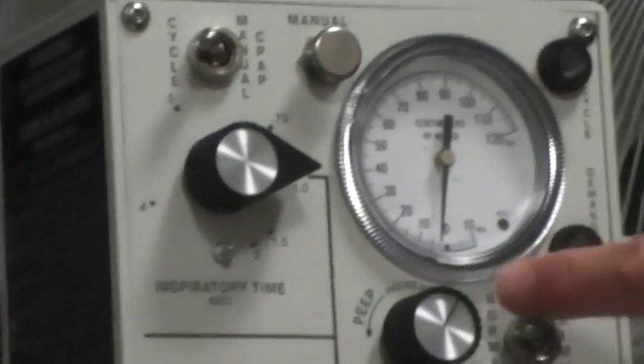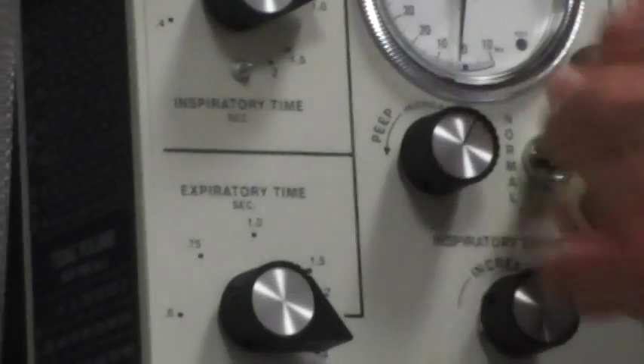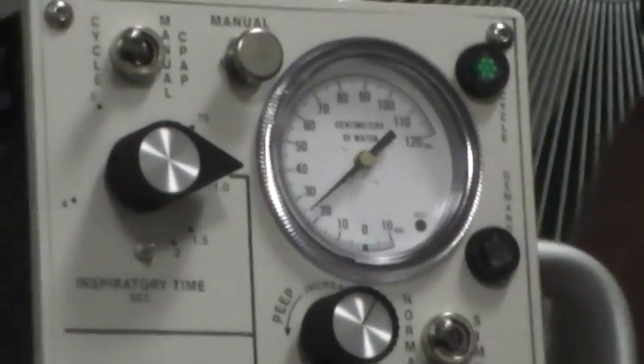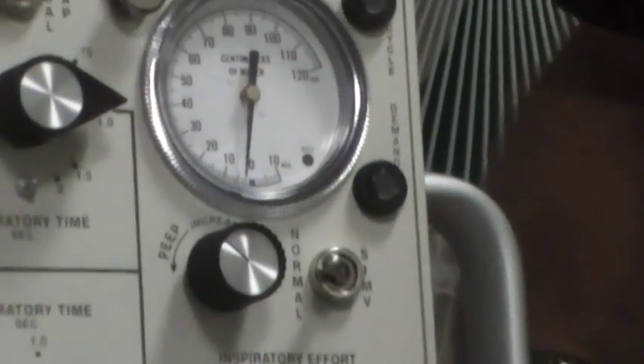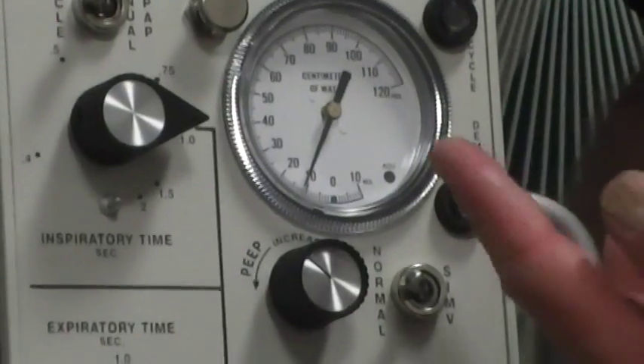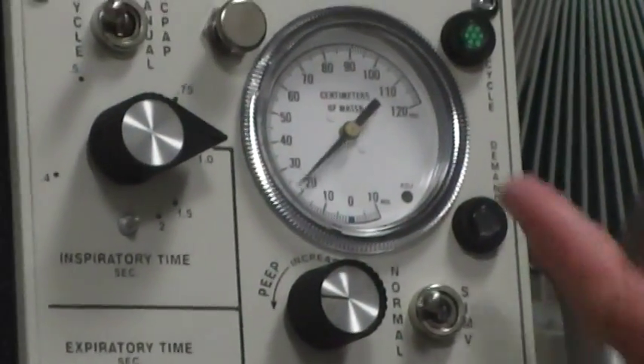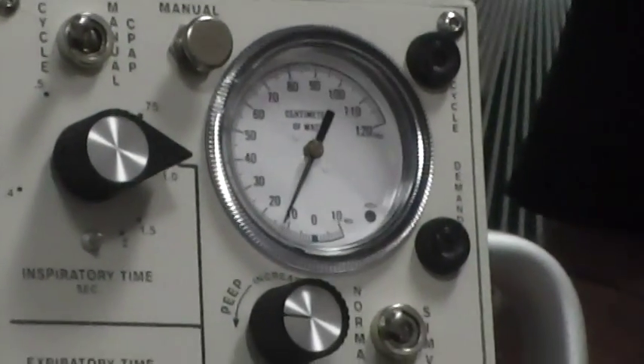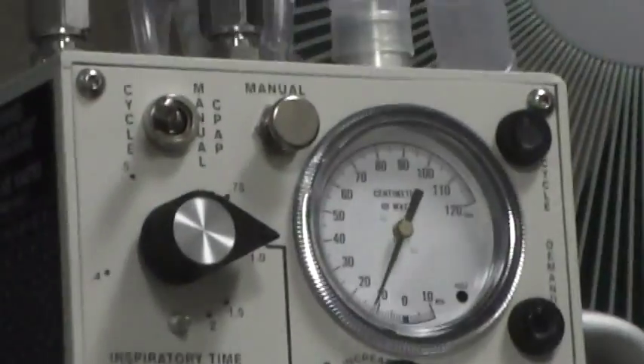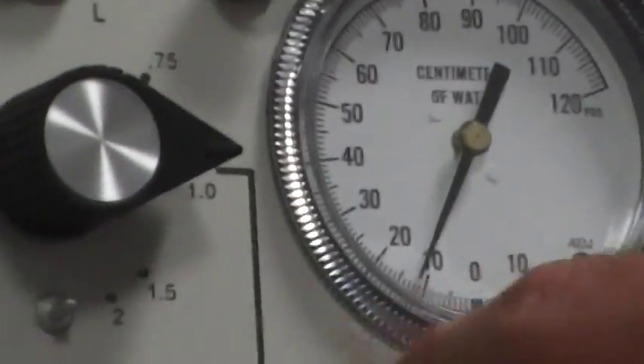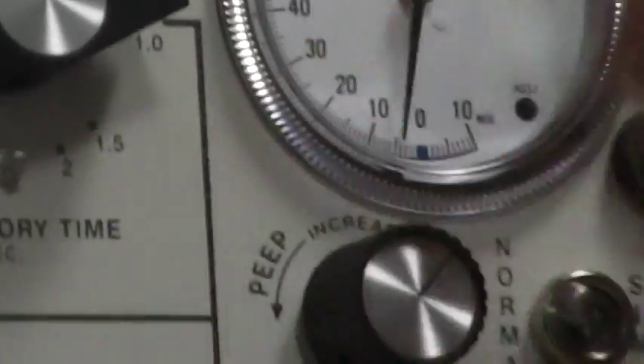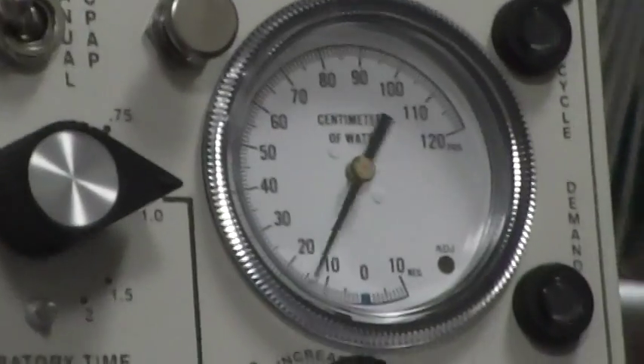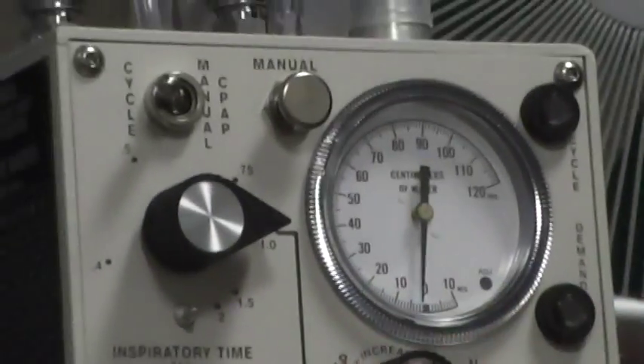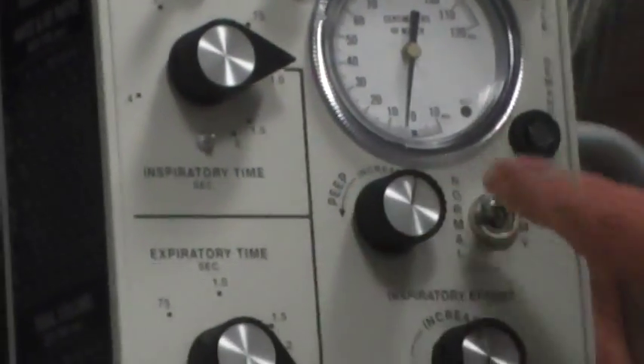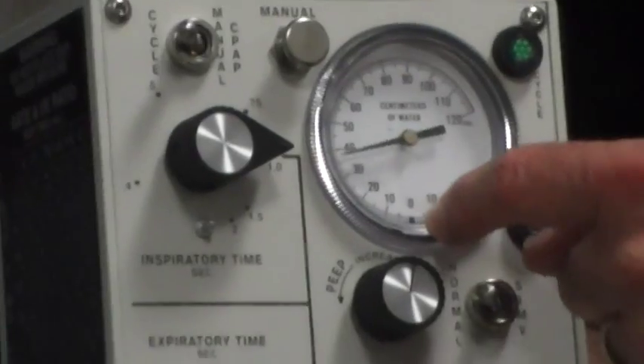So I'm going to set PEEP. With PEEP, you'll see the knob that says PEEP greater this way or less that way. You just look at your manometer, and if you want more PEEP, you turn it up. You always have to wait until the next breath, because you can't add PEEP to the breath in progress. You can always take it away, see how I turned it down? You can always remove the pressure from the circuit, but you can't add it until the next breath happens. For a PEEP of 5, you just turn it until the needle settles at 5.